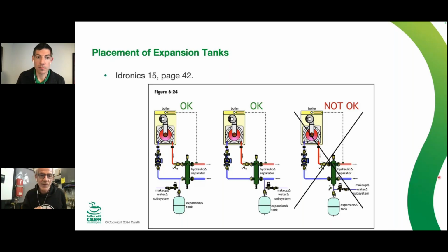So why we pump at that boiler is because the pressure differential that the circulator adds to the system when it fires up goes into the boiler to overcome the pressure drop of that coil. So we want to use our pump delta P pressure differential. Anytime a circulator starts up, it increases the pressure on the outlet side. If you had a pressure gauge right there and you plug that pump in, you would see it would go from maybe 12 pounds fill pressure up to 18, 20 pounds, depending on the size of the pump. We want that to go in through that tight heat exchanger, so we're sure that we get flow and we scrub that heat exchanger, keep it clean, scrub the heat out of it so it doesn't overheat.